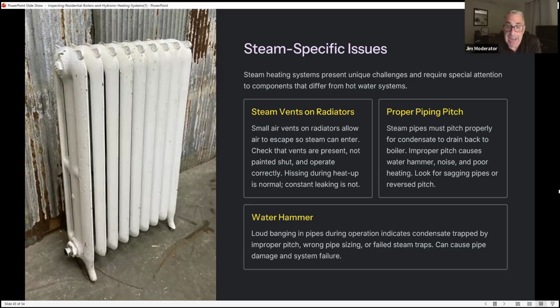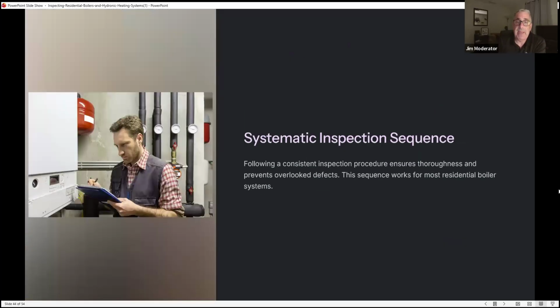Water hammering, loud banging in the pipes during operation, indicates condensate trapped by improper pitch, wrong pipe sizing, or failed steam traps. This can cause pipe damage and system failure. If we're following a consistent inspection procedure, this ensures thoroughness and prevents overlooked items. This should be for all your inspections.